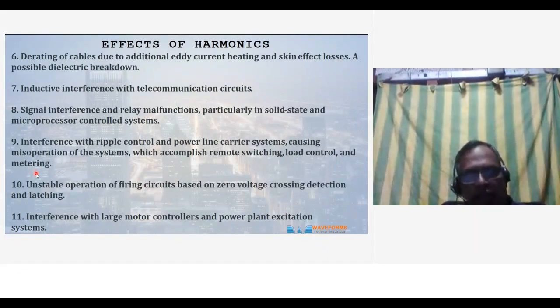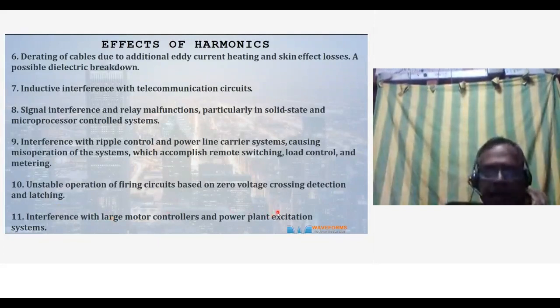Unstable operation of firing circuits based on zero voltage detection and latching. Sometimes there's a voltage drop to zero for a few nanoseconds or microseconds, and this zero voltage is sensed and it causes mis-operation. And interference with large motor controllers and power plant excitation systems. So these are all the ill effects of harmonics.